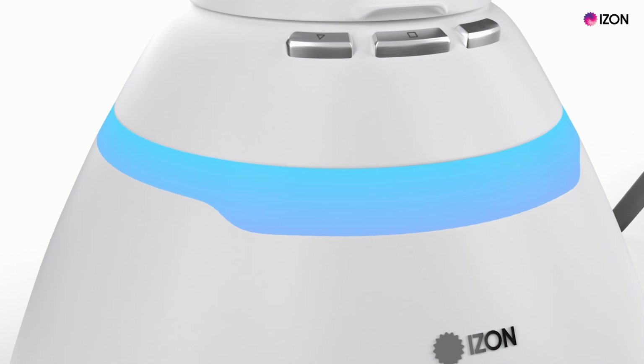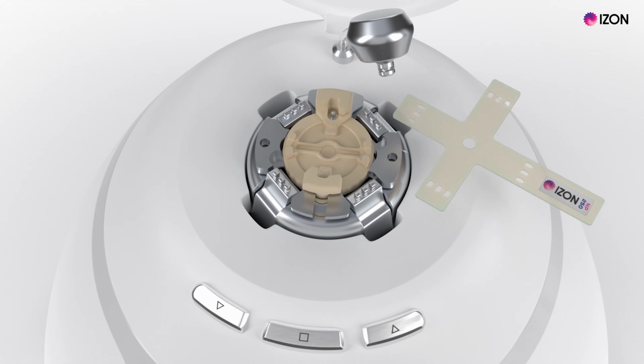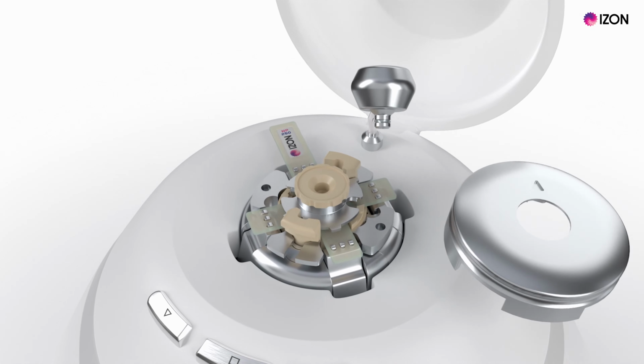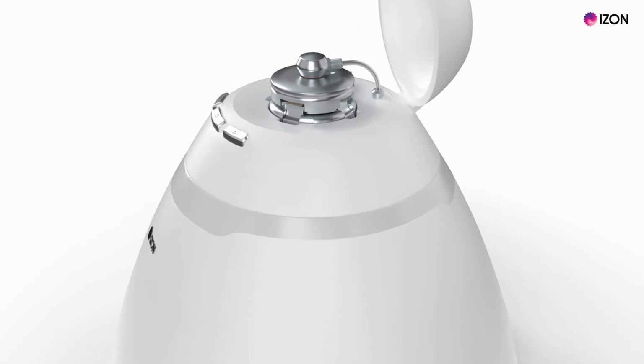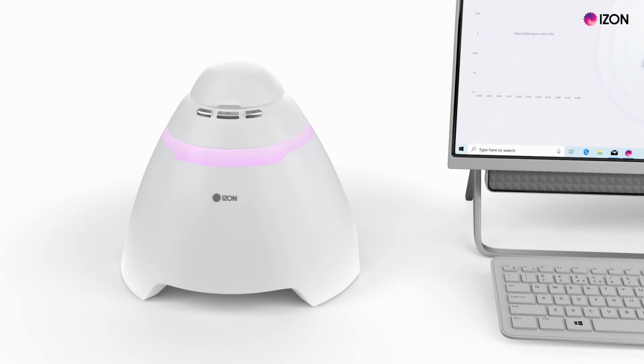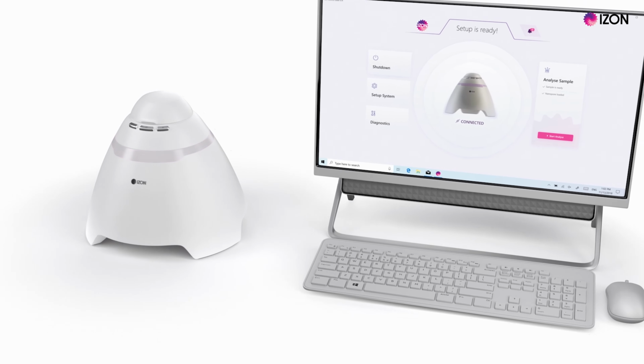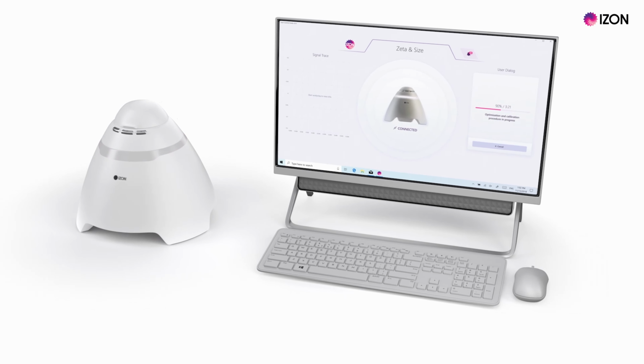The Exoid Control Suite software walks users step by step through the entire setup and measurement process. Upon selecting nanopore setup, the software will prompt users with what they need to do to get their system ready for measurements. The user is guided through wetting and coating the nanopore to get a stable baseline. Then the nanopore is characterized by the software to give its detection range. This entire process usually takes about 20 to 30 minutes and gives the user an accurate summary of the nanopore's measurement capabilities at each stretch setting.